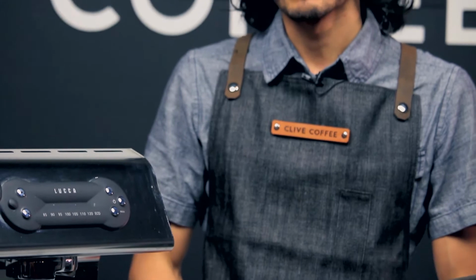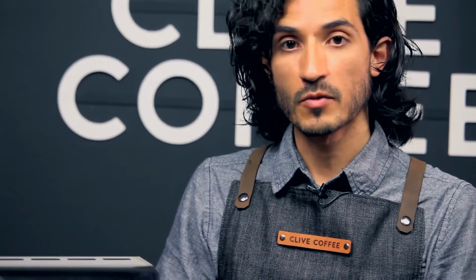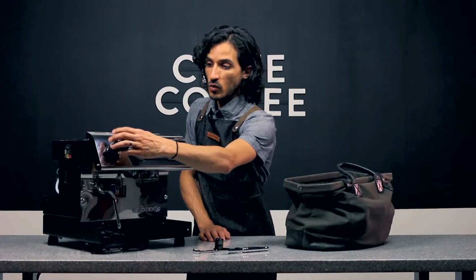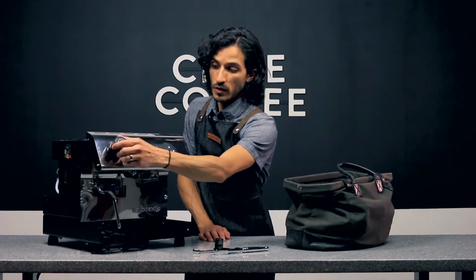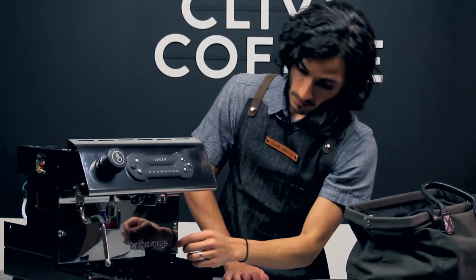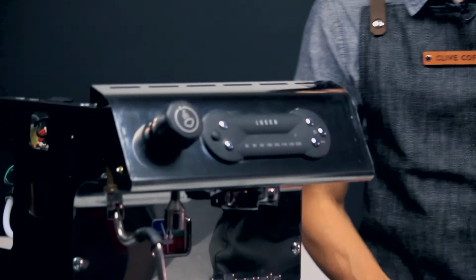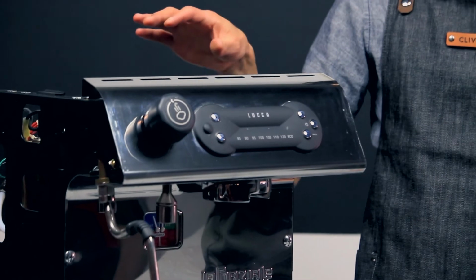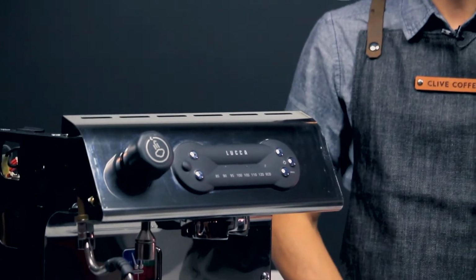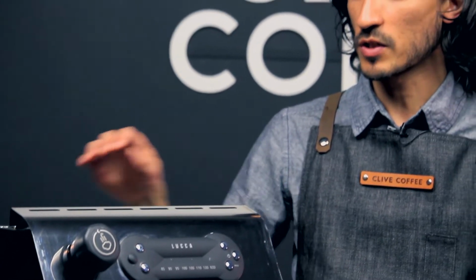Before you begin this process, you're going to want to cool off the machine, open up your steam wand, and make sure the pressure is completely relieved. You can double check your pressure gauge and make sure that's at 0. You'd want to let the machine cool off quite a bit, maybe leave it for an hour or so, to make sure your steam boiler won't burn you when you're in there with tools and might be touching that boiler.